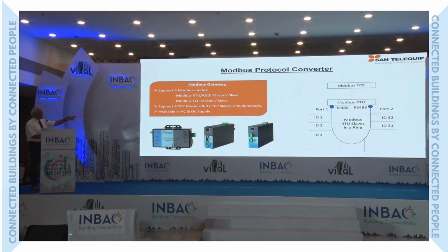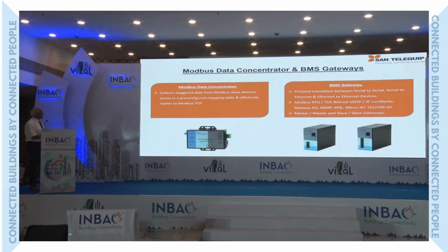The schematic shown is a typical design we have done. Modbus RTU serial port does not allow redundancy, but in this design we can provide redundancy for a simple RS-485 loop. It's a very handy tool, especially in energy metering applications where your cable runs very long distances. These are our BMS gateways.